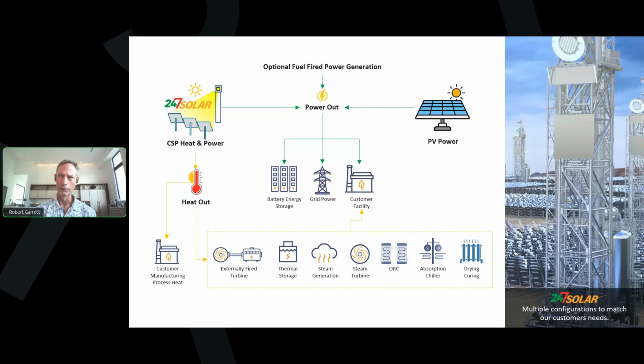You'll also see absorption chilling there. That's a use case we're really investigating heavily in the data center environment, because we can actually use our waste heat to drive absorption chillers and reduce about 20 to 30% of the electrical load that would be required to operate the data center, which gives them a tremendous opportunity for savings.